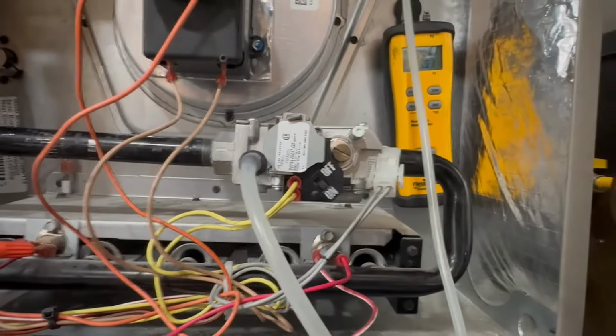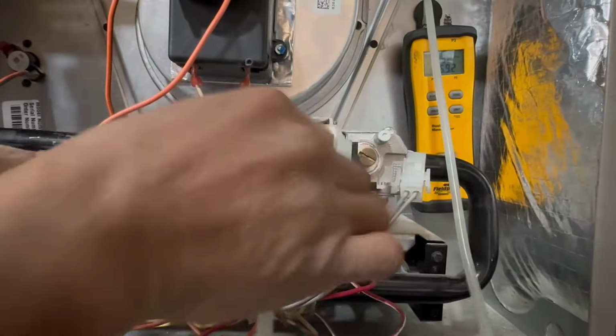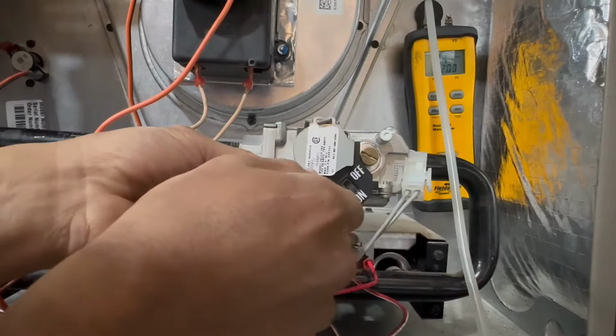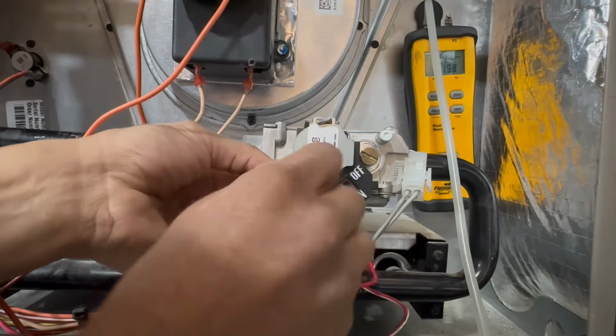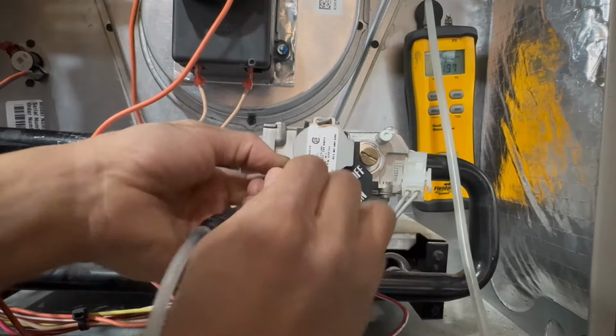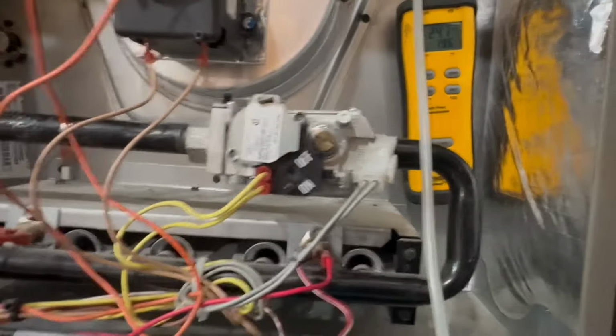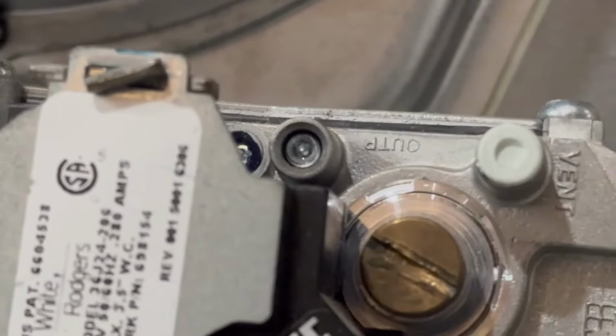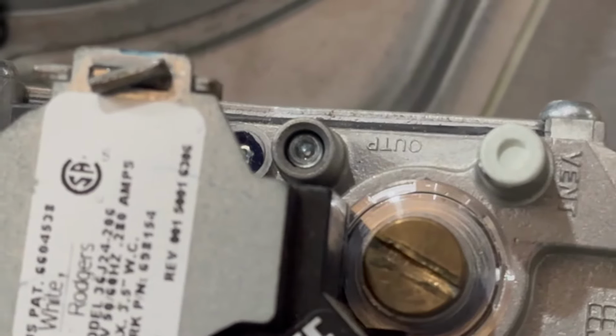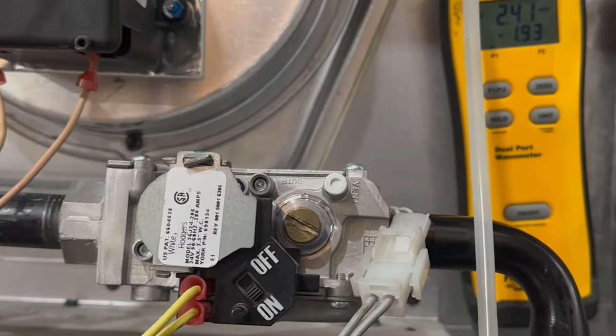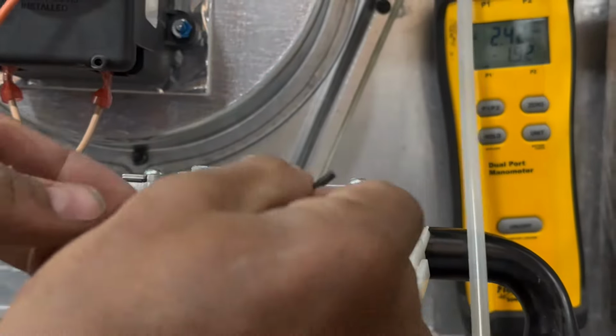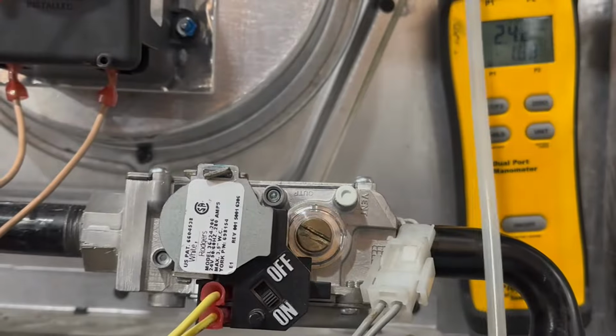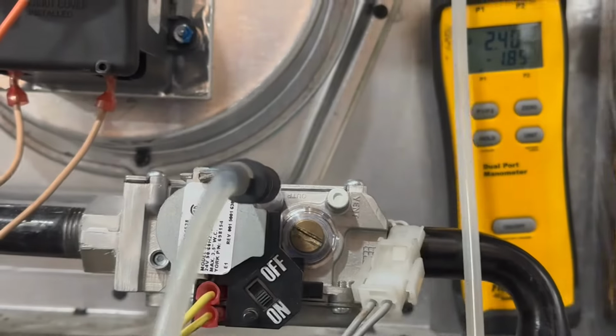Okay, so now we're gonna do the inlet, right? So I'm gonna go ahead and open this, and you see I'm getting some gas coming out. So you gotta make sure you close this, righty tighty. Okay, that's good. So the other one, the outlet, is right there. You see, it even says out, P, right next to it. So same thing. I'm gonna go ahead and crack that open. So obviously right now, we're not getting anything out because we're not sending voltage to the gas valve, but I'm just gonna get it ready for you guys so you guys can see.